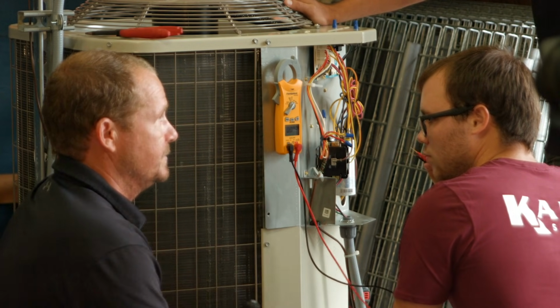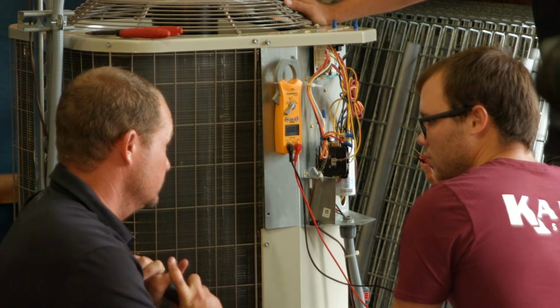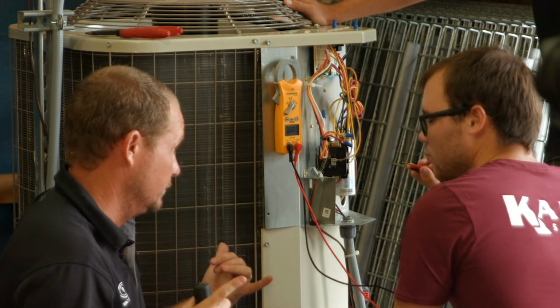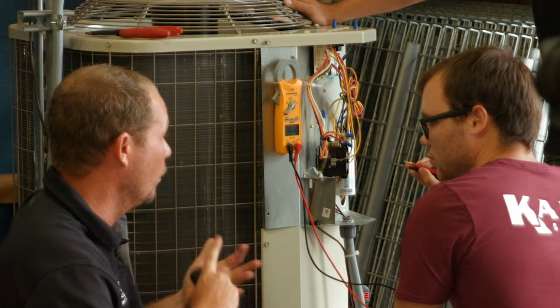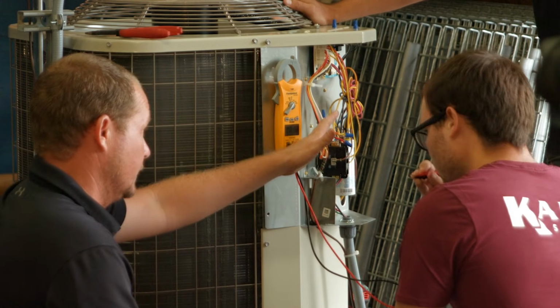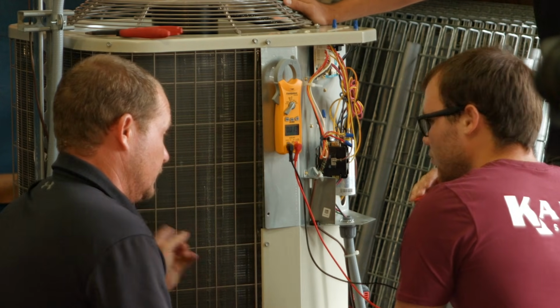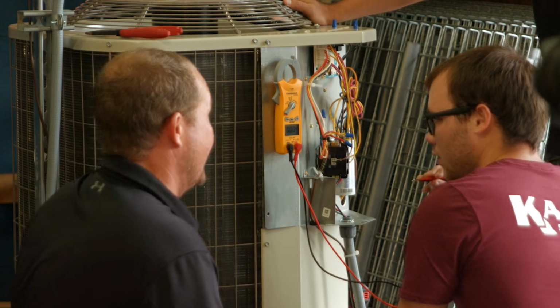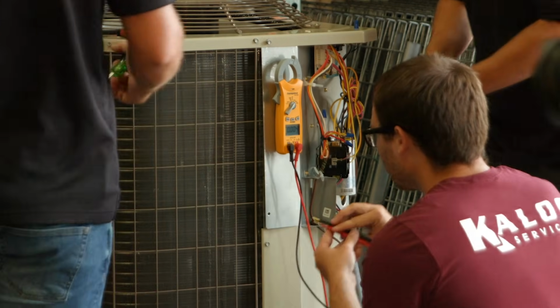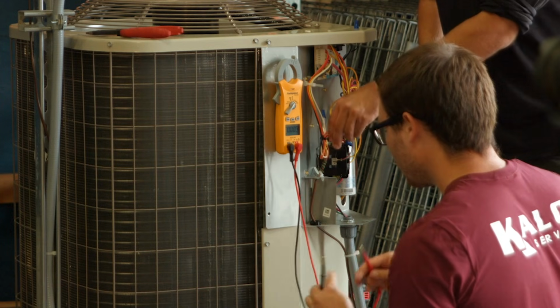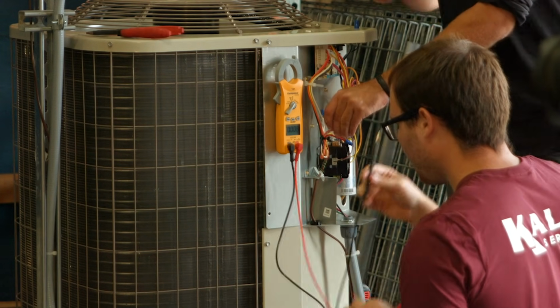So now we still suspect, could it be that the thermostat isn't sending an O signal at all? We don't know, it could be. Or is it that it's broken in the conductor between the air handler and the condenser? So now I would back in and check it at the air handler. And you could have started at the air handler. I tend to start at the air handler, but either way is fine.